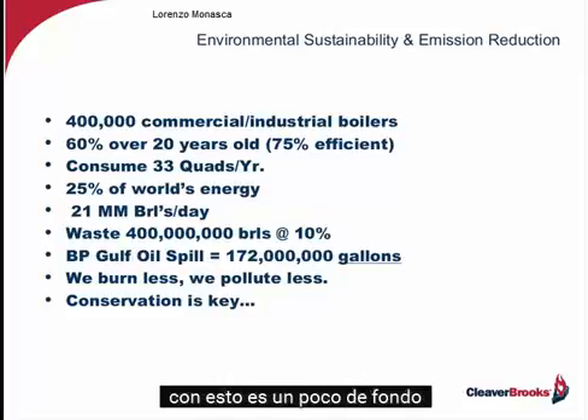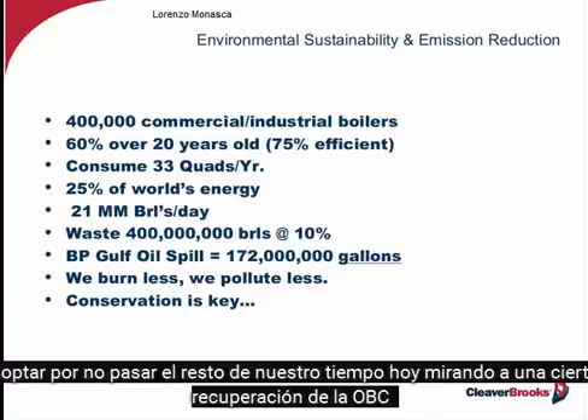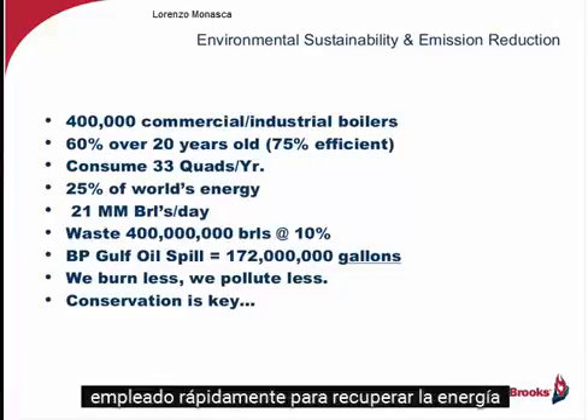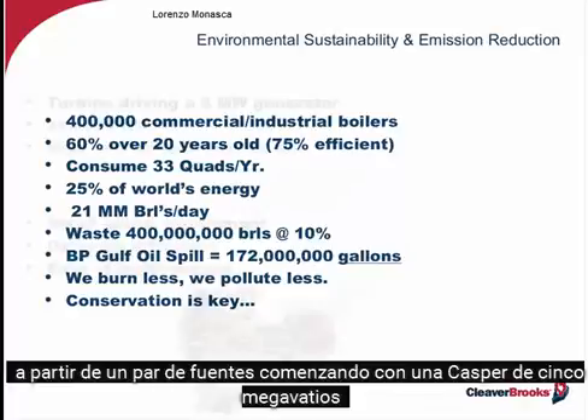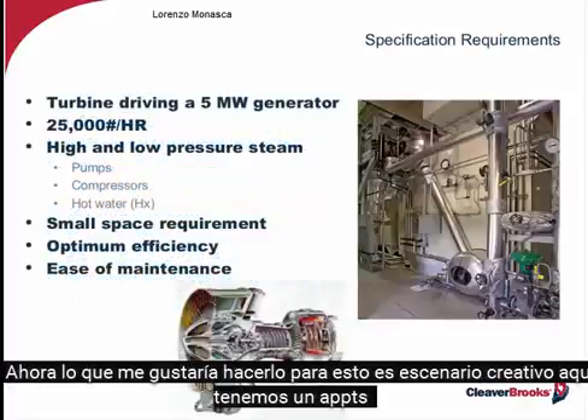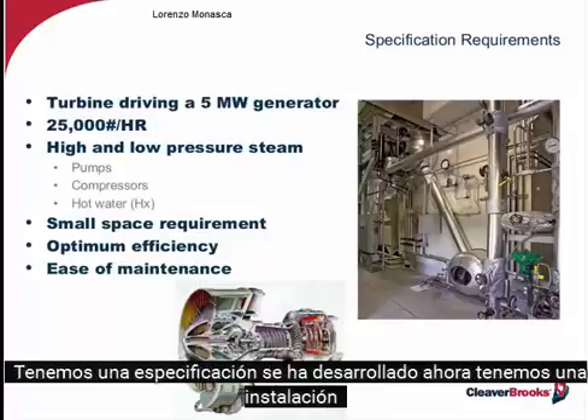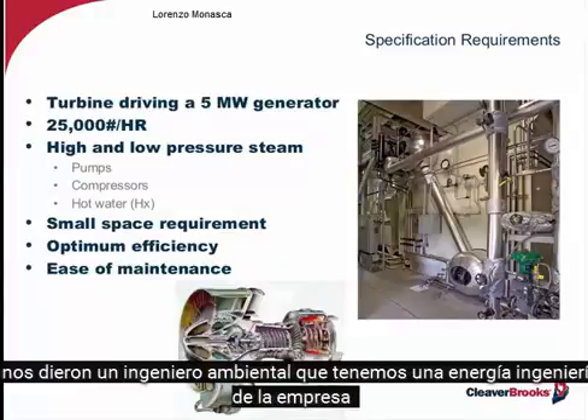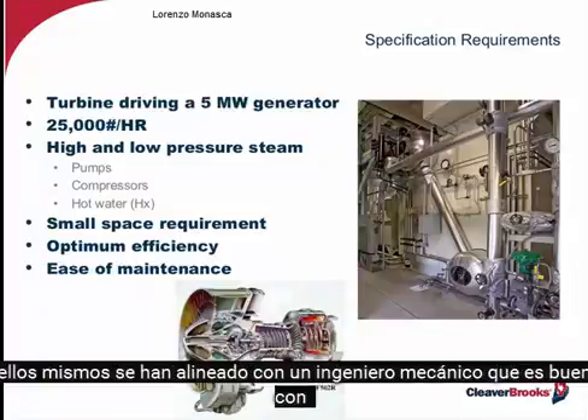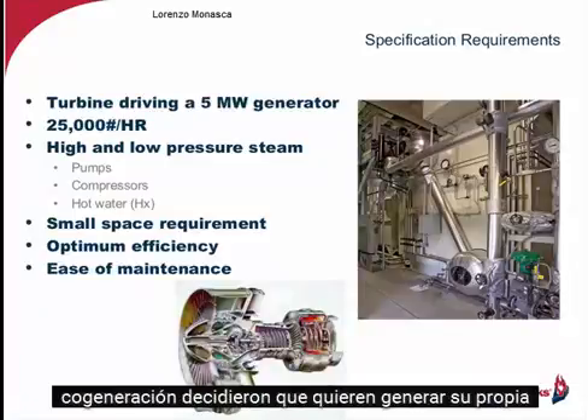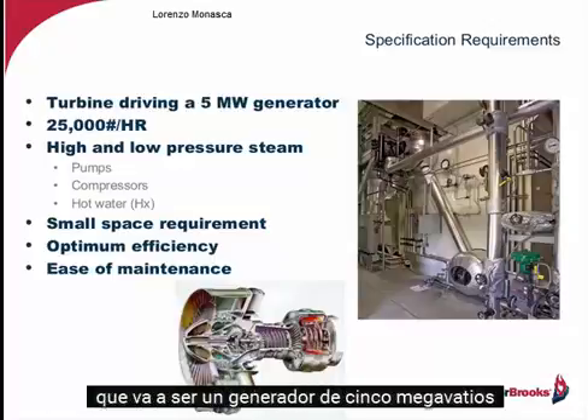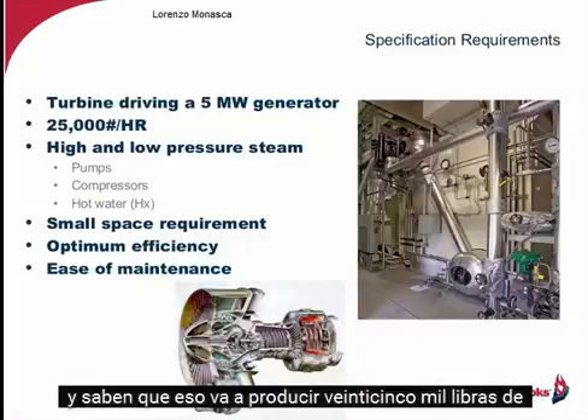So with this as a little bit of background, let's spend the rest of our time today looking at some of the heat recovery equipment employed to recover the energy from a couple of sources, beginning with a 5 megawatt gas turbine. Now, what I'd like to do for this is create a scenario here. We've got a specification that's been developed. We've got a facility engineer, an environmental engineer, and an energy engineer in a company. They've aligned themselves with a mechanical engineer that's good with combined heat and power. They've decided they want to generate their own electricity. It's going to be a 5 megawatt generator. And they know that's going to produce 25,000 pounds of steam an hour.